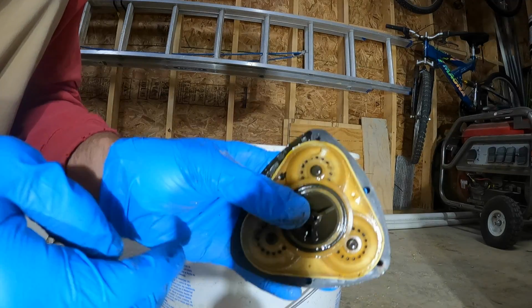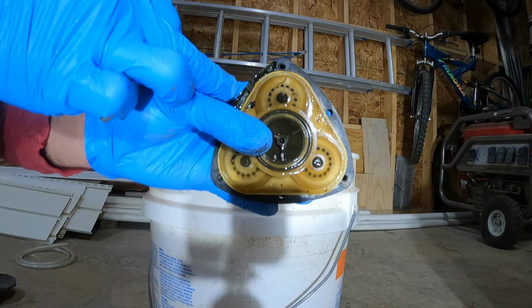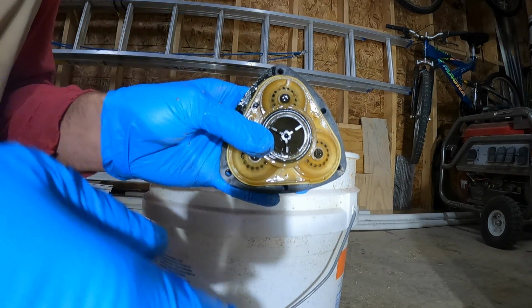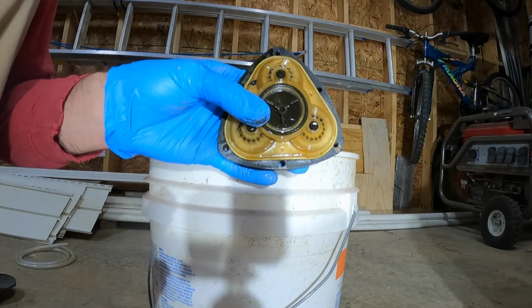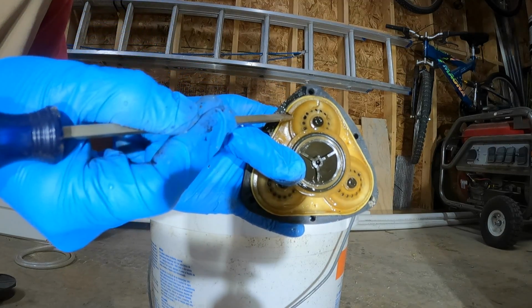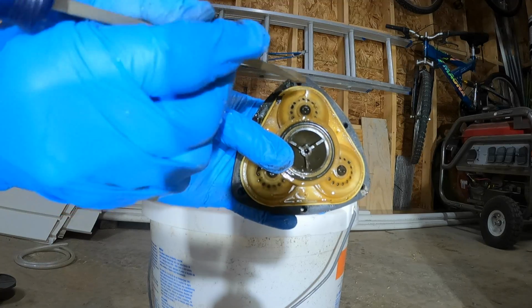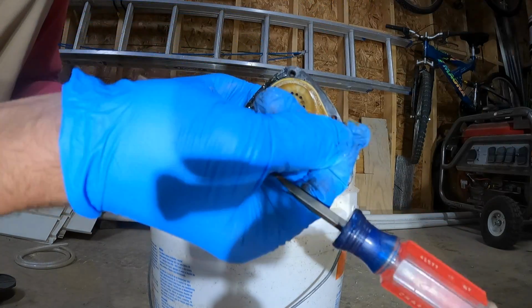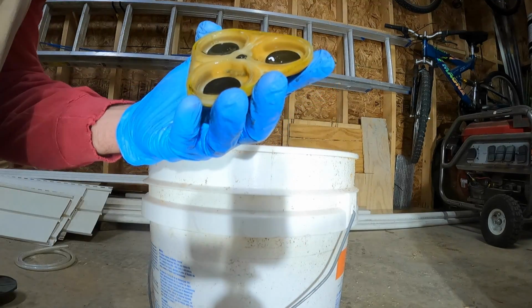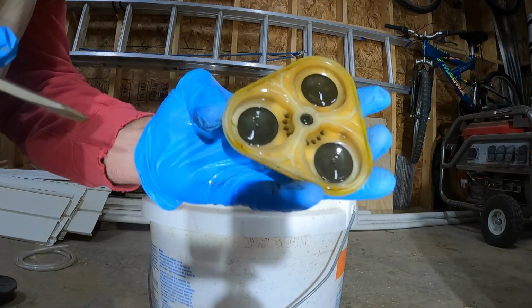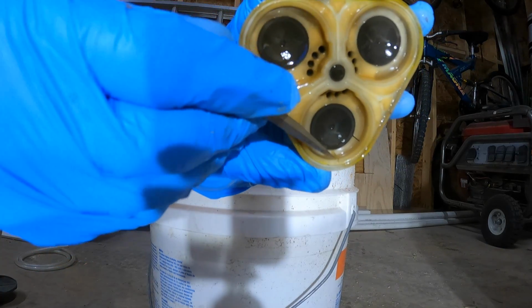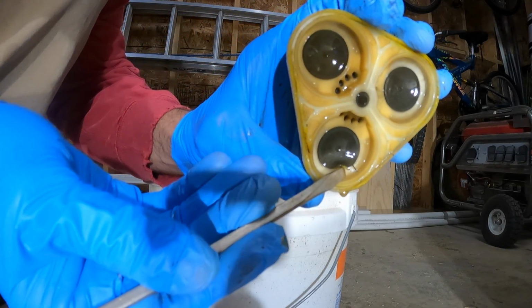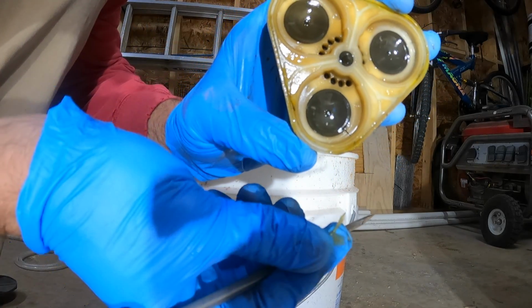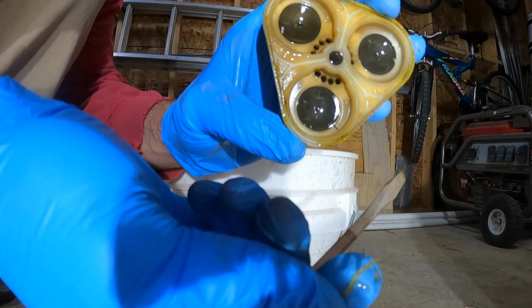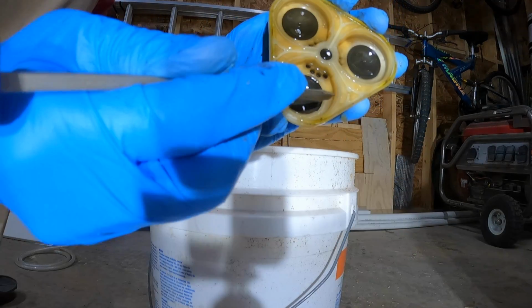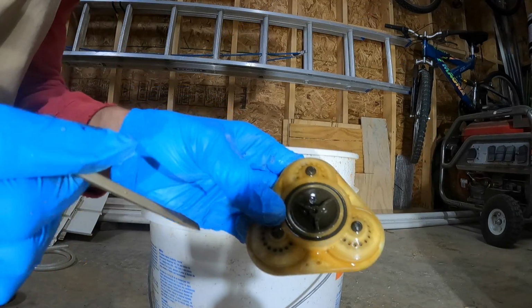So if you take a look at the diaphragms on the pump, you can see I do have some stuff inside the pump itself. We're just going to go through and clean it out, but I'll show you there's a little piece of a leaf in there. There's some type of material. If you can see it on this lower diaphragm here, there's a piece of trash right there. It's hard to tell what that really is. It looks like a piece of plastic. Maybe that came off one of the internal portions of the pump. And then there's another piece of trash. So overall, it looks pretty clean.